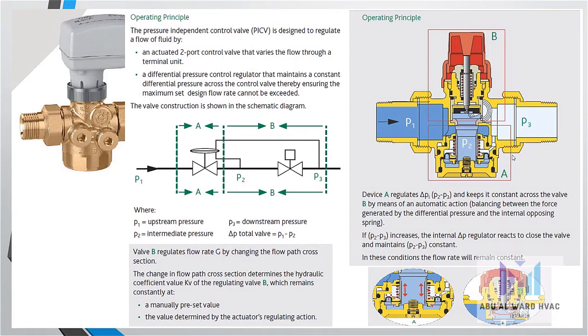The pressure independent control valve PICV is designed to regulate a flow of fluid by an actuated 2-port control valve that varies the flow through a terminal unit, and a differential pressure control regulator that maintains the constant differential pressure across the control valve, thereby ensuring the maximum set design flow rate cannot be exceeded. The valve construction is shown in the schematic diagram, where P1 is the upstream pressure, P2 intermediate pressure, P3 downstream pressure, and delta P for the total valve equals P1 minus P2.